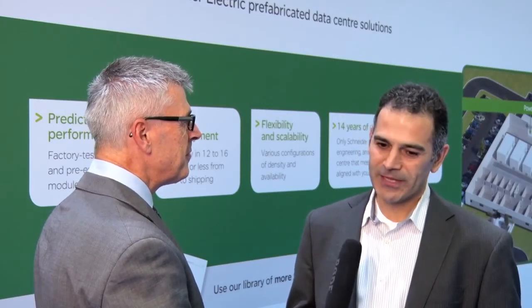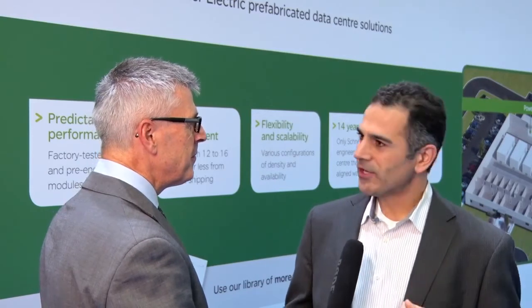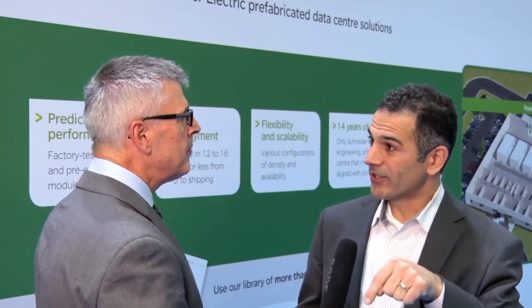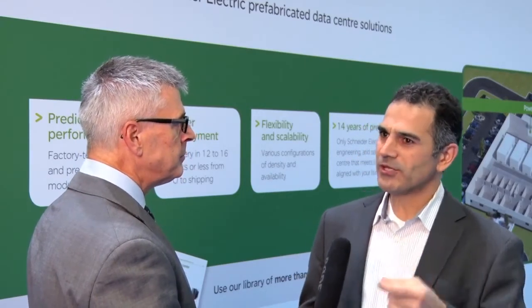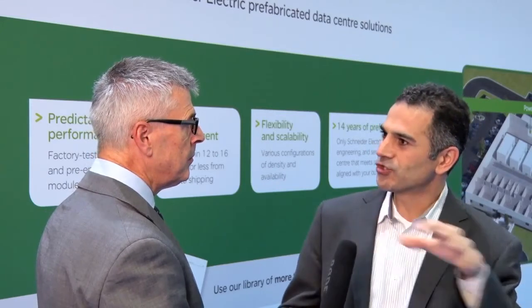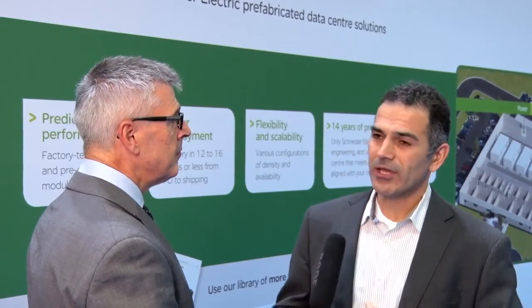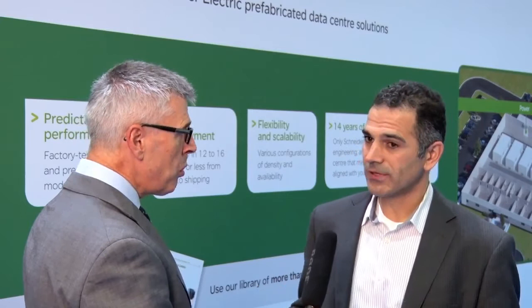Another example is we measure the return temperature of a data center back at the air conditioning unit. Now, why do we measure the return temperature and then control the supply air to our IT equipment when it's the IT equipment that really matters, right? Now, this goes back to when we had mainframes, and they basically mixed all the air in the room and kept it at an even temperature.